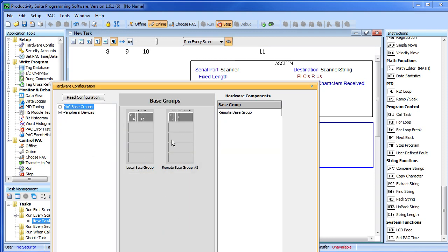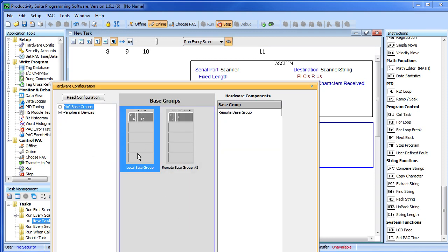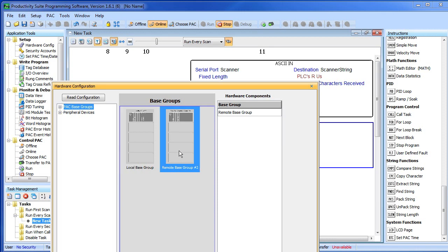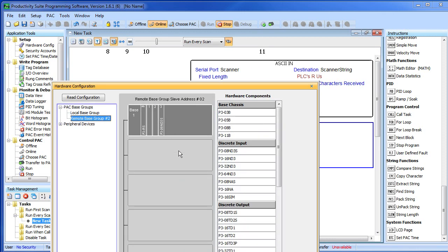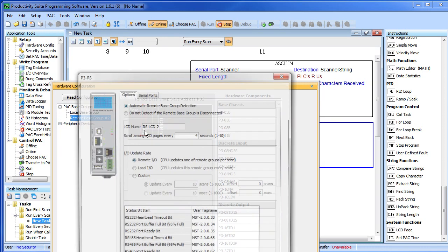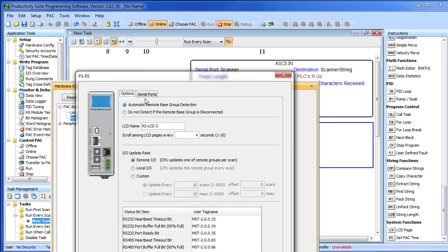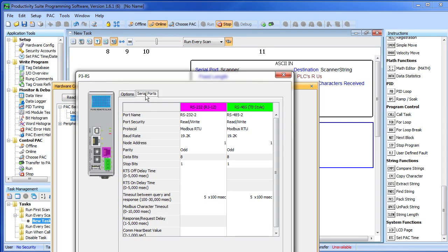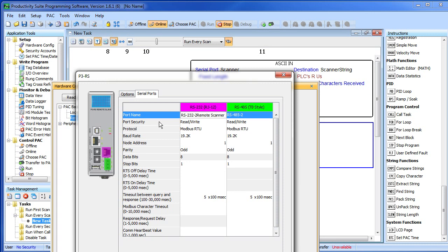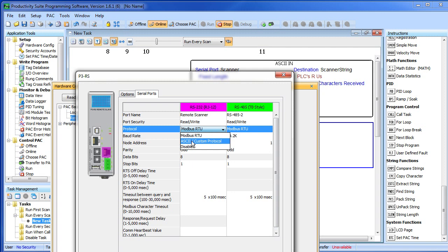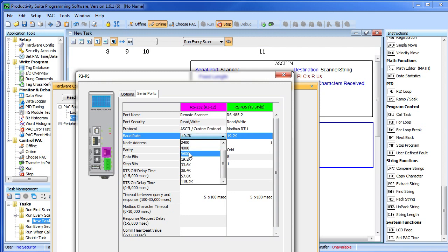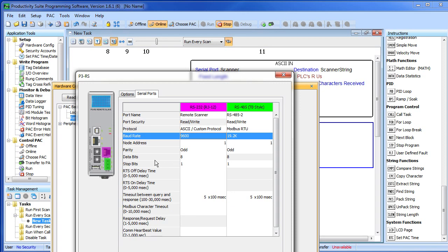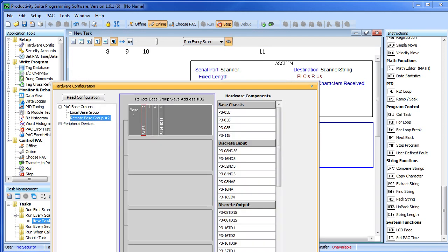Here are our two bases—here's our local base and our remote base. I double click on the remote base and I see how it is populated, double click on his processor and set up the serial port. Its name is currently RS232—we can do better than that. Let's call him remote scanner. We want to make sure his protocol is ASCII. Set him up for the right baud rate—odd 8 and 1. So now our remote slave serial port is set up and ready to go—that was step 1.